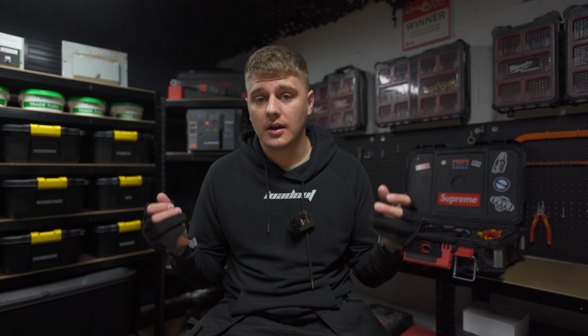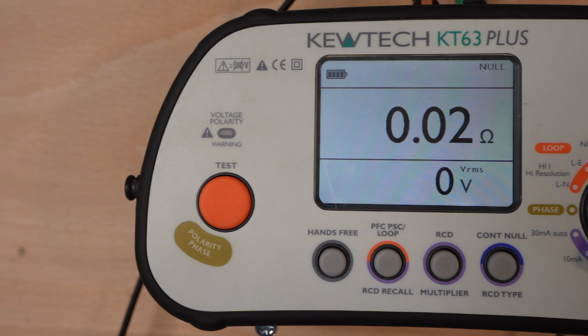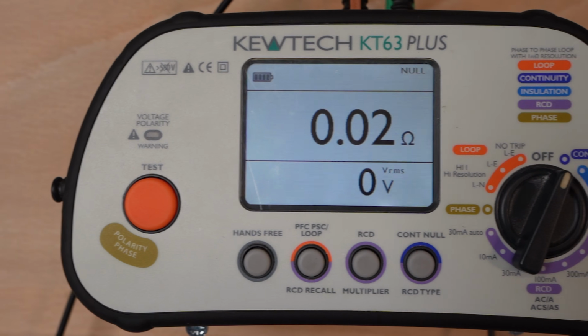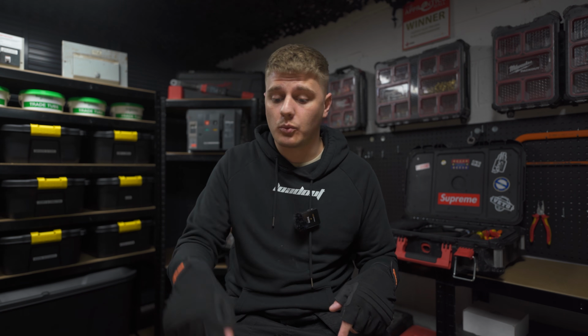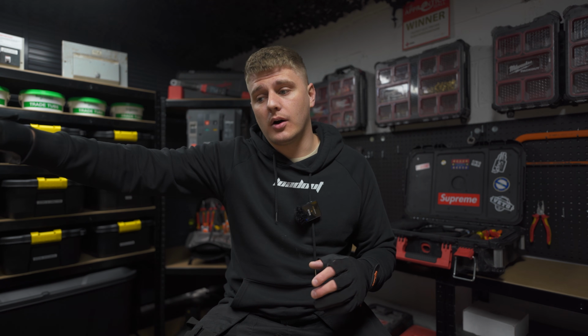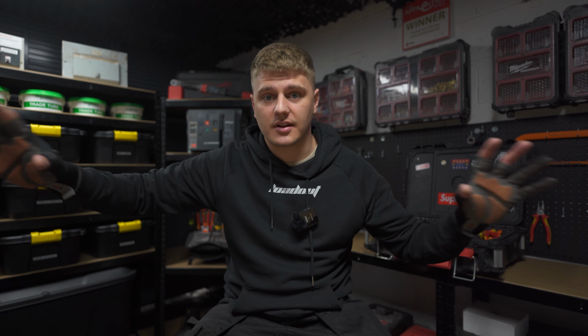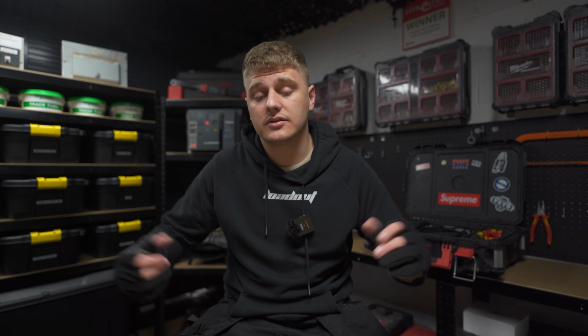Firstly, two separate bonding conductors to two separate exposed conductive parts or extraneous conductive parts will test out fine if left connected, even if there's a break in one of them. It's effectively going to perform a loop, so whatever bonding clamp you test at, you're going to get continuity there, thus providing a false reading. Because if that parallel path was removed by a change in pipe work, a change in something out of your control, out of the installation, then you're going to have a broken bond there, which obviously gives rise to potential.